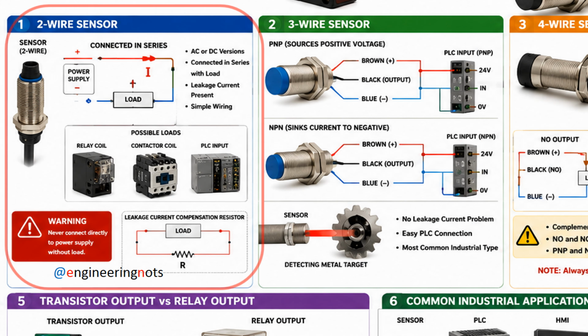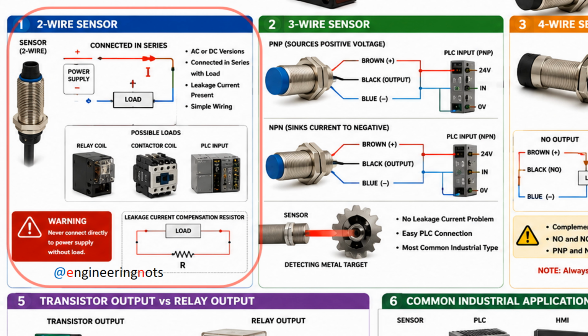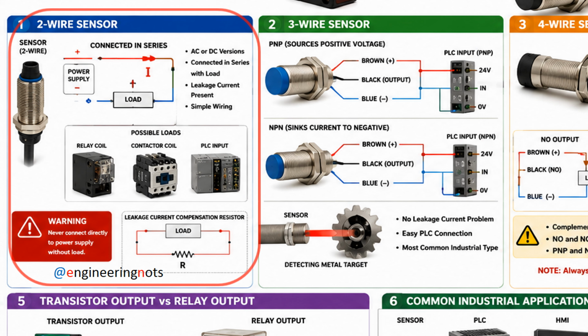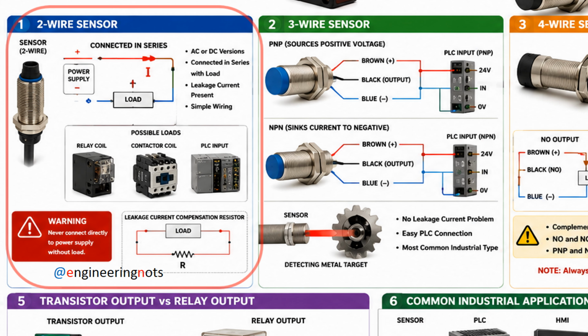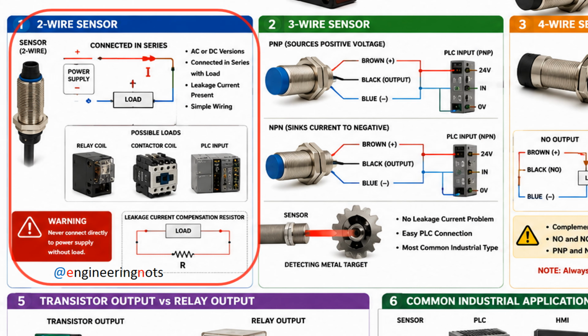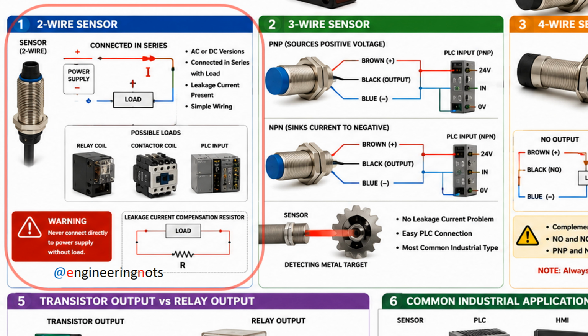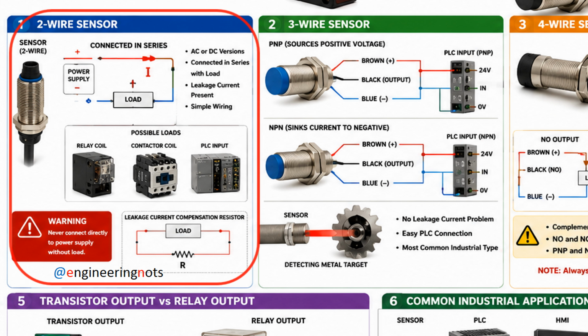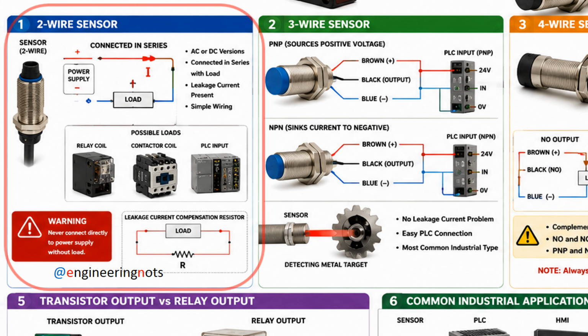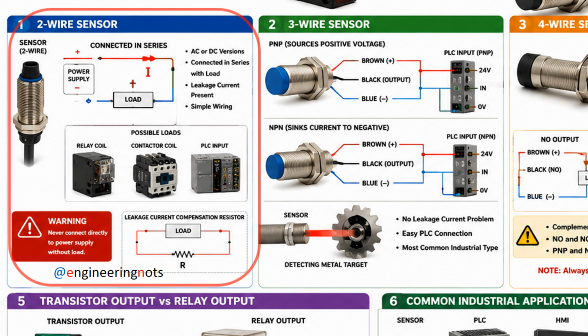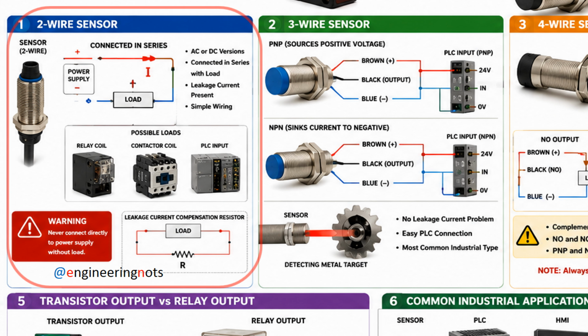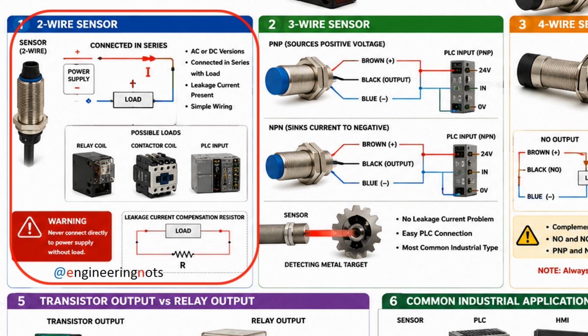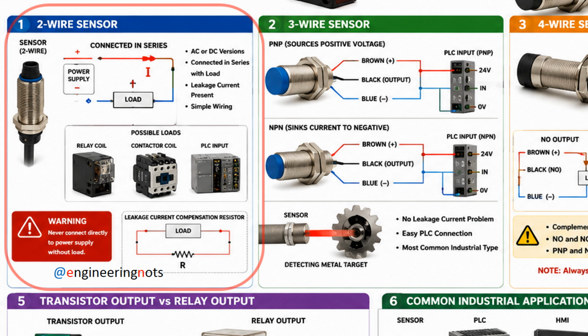Now we move to the first group, the two-wire sensors. These are the simplest type of industrial sensors. These sensors are available in both AC and DC models. They may also be manufactured as cable-type or connector-type sensors. How they work. A two-wire sensor is connected exactly like a switch in series with the load. In other words, it must always be connected in series with the load. The circuit path is as follows. Power supply. Load. Sensor. Return to power supply.